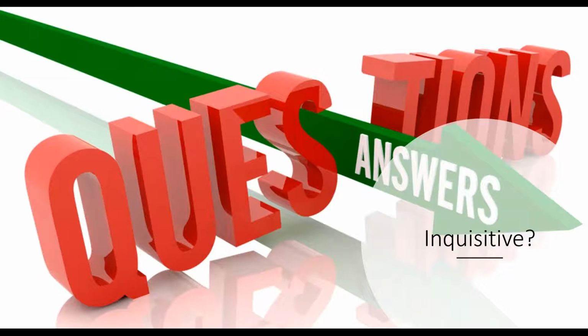Now this question I'm also confused on that aspect, and mainly this is from customers, because a couple of customers also ask that we need to get the octave band frequency of the transformer. What we do is a general A-weighted value, which is a dBA measurement. If you're talking about the A-weighted and the Z-weighted, then for sound measurement for human ears, the base method is to do the A-weighted, so it's a dBA measurement. The Z scale or octave band frequency at Z scale mainly helps you identify at which frequency the transformer's noise gives a higher value. So it is just to identify the frequency correlation to the sound.